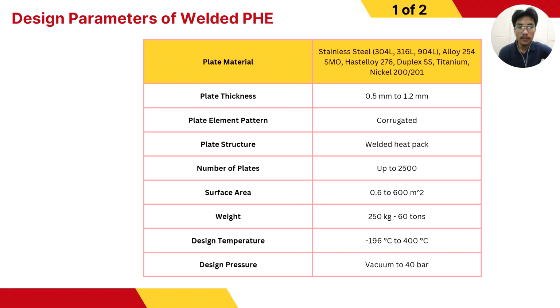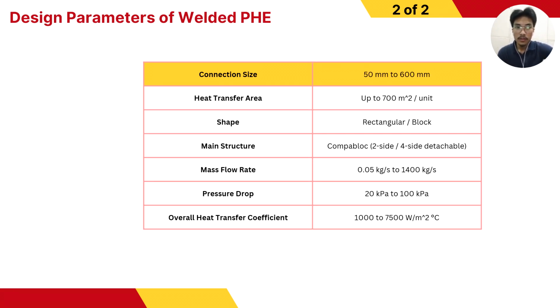This is the second part of the table for the design parameters of a welded plate heat exchanger. For continuation, the connection size can range from 50 millimeters to 600 millimeters. So this specific parameter is highly dependent on the manufacturer or companies that create the welded plate heat exchangers. Next, heat transfer area. It can be up to 700 square meters per unit. So the heat transfer area is mainly dependent on the number of plates that are used on a welded PHE as well as the size of those plates.